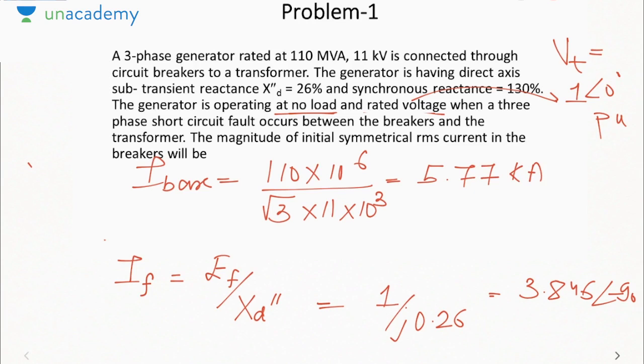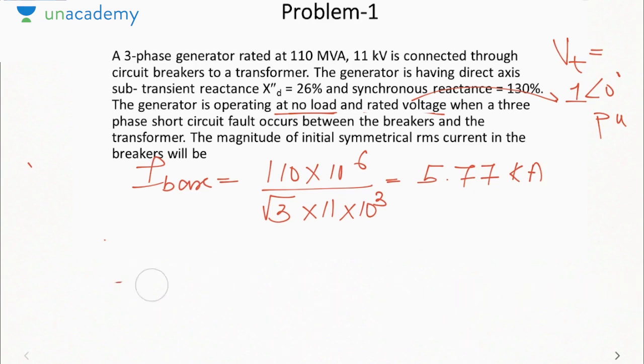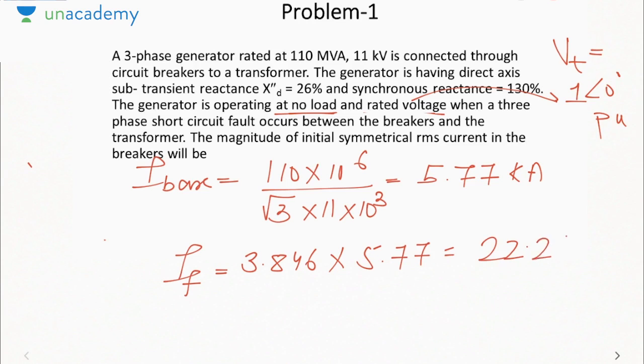Now what will be the actual value of current? It will be the base current multiplied by the per unit current. The per unit current is 3.846, so the fault current is 3.846 into 5.77. It will come out to be 22.2 kiloamps. Remember, whenever we are talking in per unit, the per unit current will remain the same throughout the system, because in PU the entire network is connected in series and there is no transformation ratio. But if you are talking about actual current, then first see in which section you are trying to determine the current and use the base current for that particular section, because whenever there are transformers, you have to use the base current of a particular section to determine the overall current. Now let us move on to the next problem.